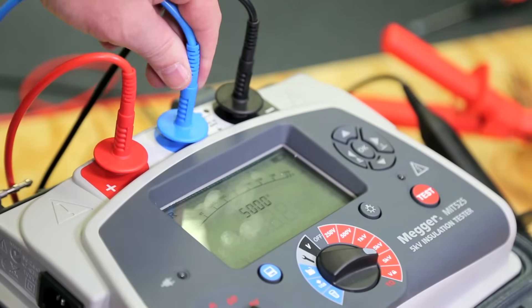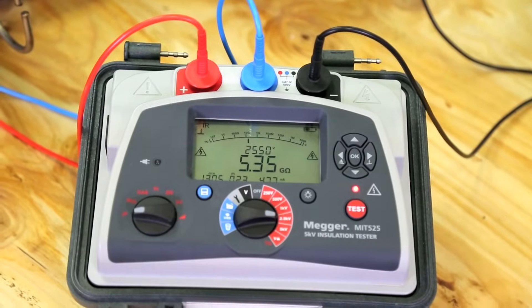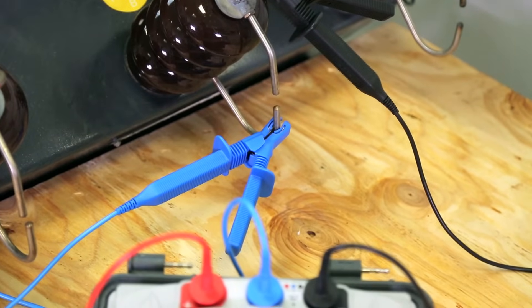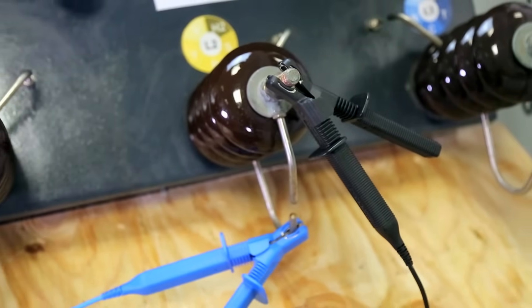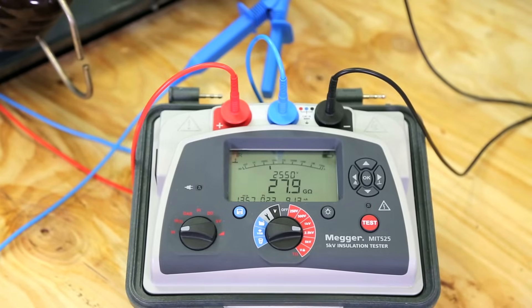The guard terminal ensures you measure the insulation that you want to measure. It measures and discounts any surface leakage current. It is key to the accuracy of the insulation test. That's why Megger's guard terminal performance is specified and offers unmatched accuracy.